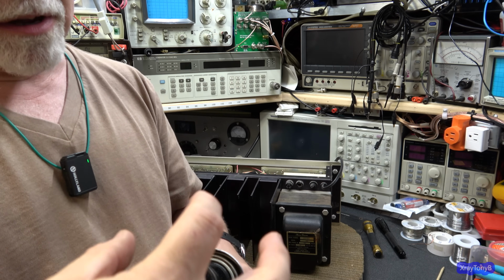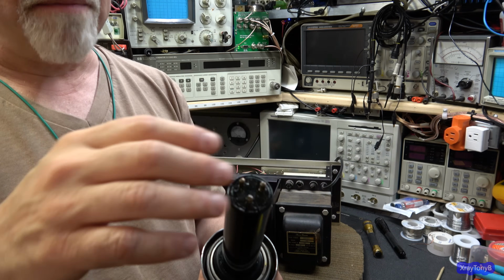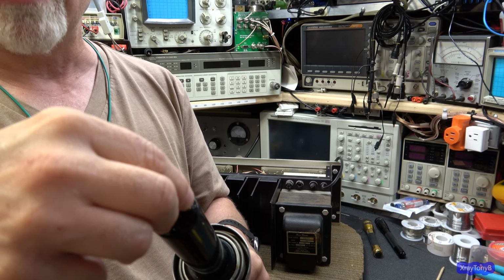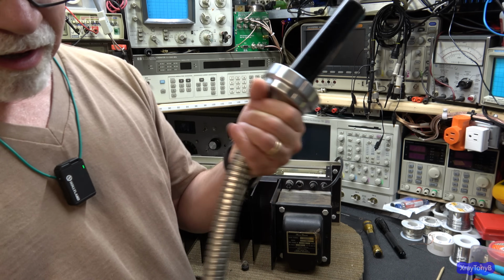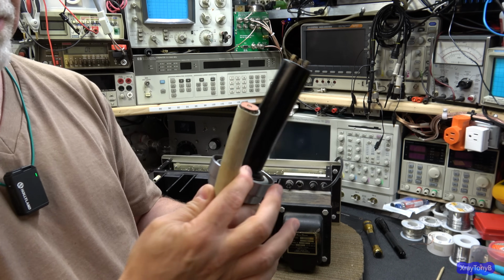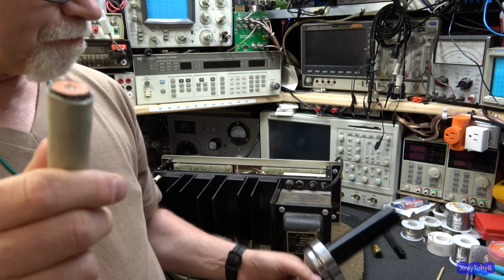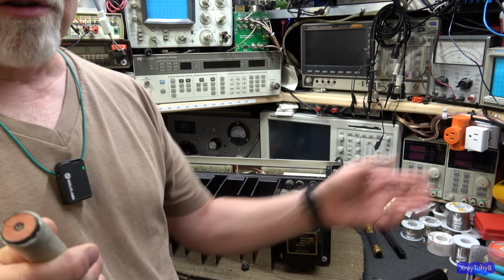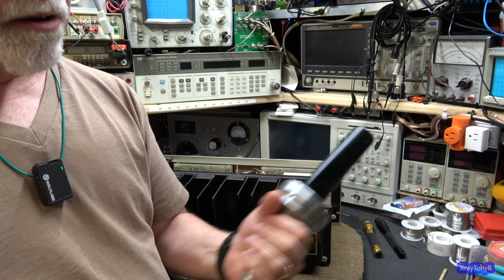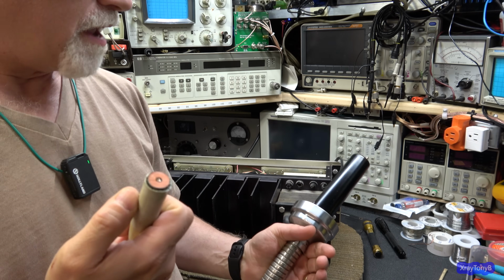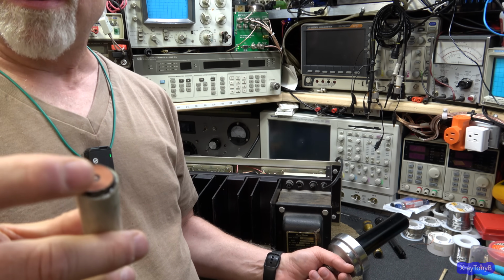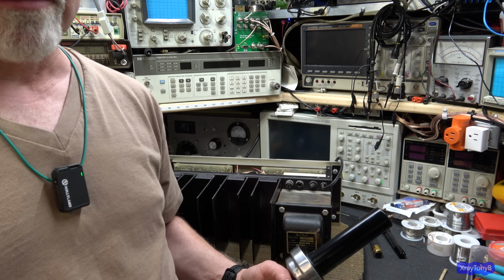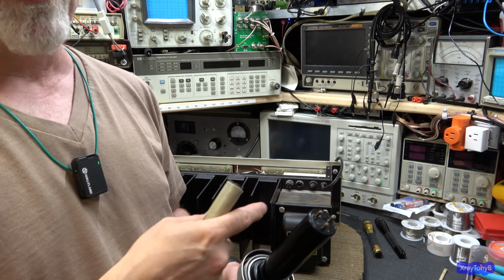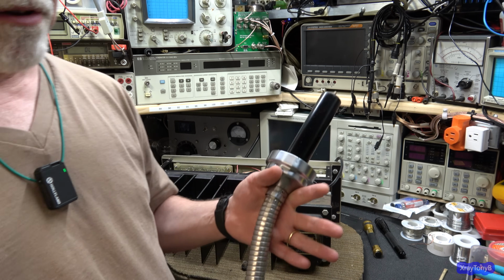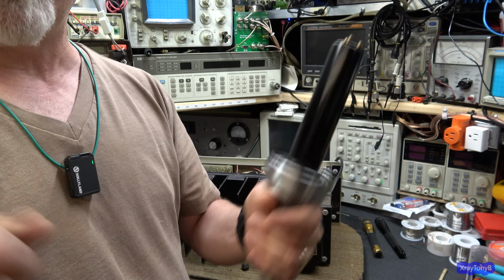On the cathode side, these 3 pins go to the filaments and also to the cathode connection. On the anode side, you use the same cable, but inside the X-ray tube housing, these 3 pins are all tied together. So they're shorted together. And what I'm doing is, we all carry one of these in our cars, so that if you're testing a tube filament, you can just pull the candlestick, as we call them, out of the tube, plug this into the cathode, and then we kind of strip these wires out, and you can hook your meter to them, and you can check the filaments to see if you have an open filament or shorted filament to the cathode cup or something like that. It's a really good test tool made out of an old cable that you ripped out of an old machine.